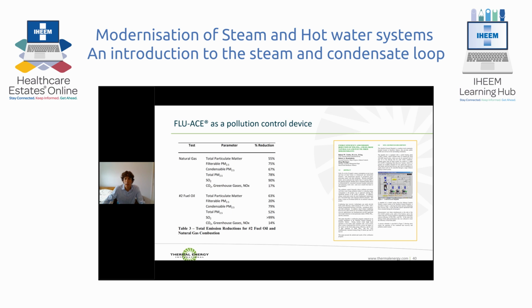In one of your handouts for today's session, there was a paper between Johnson Controls, Thermal Energy International, and a Canadian hospital studying the effects of adding a FLU-ACE to both a natural gas-fired and number two fuel oil or diesel-fired boiler. You can see a significant reduction in particulate matter and proportional reductions in all of the exhaust gases due to the savings through burning less fuel.